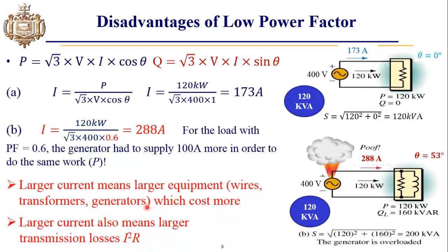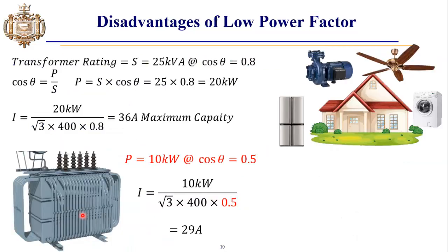The disadvantage of low power factor is that you will require larger equipment, which includes wires, transformers, and generators to feed the same load but with low power factor. And also since the load has low power factor, it will draw more current and there will be more transmission losses, as the transmission loss is equal to I²R.